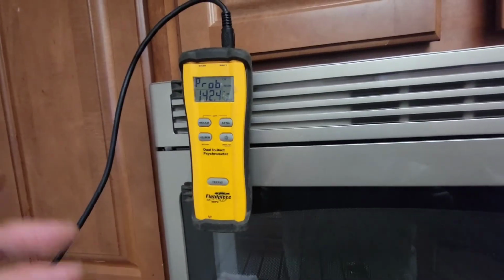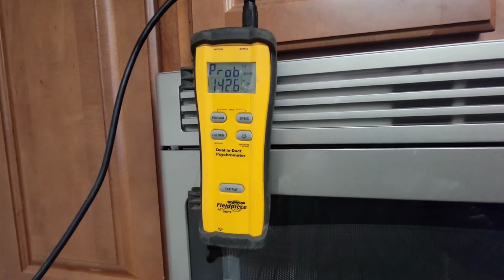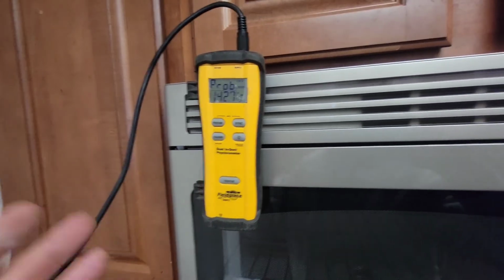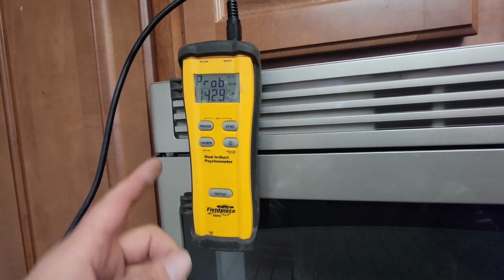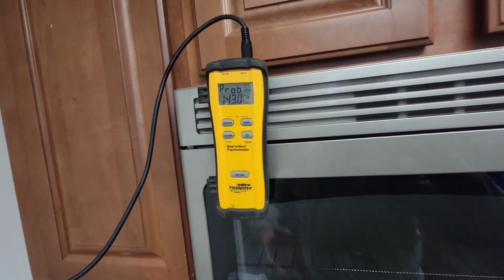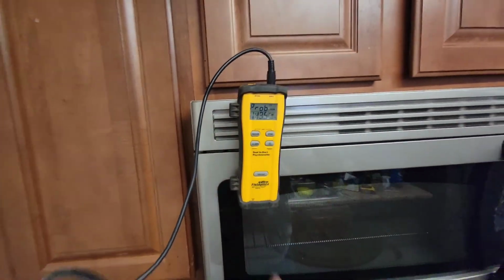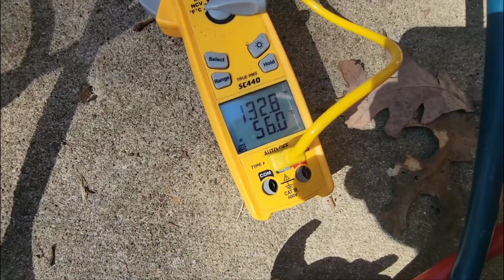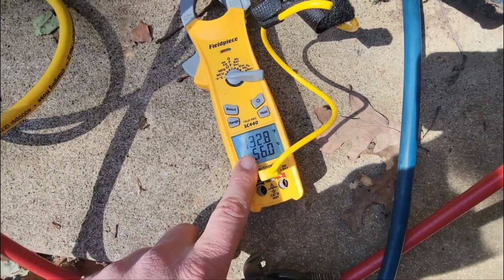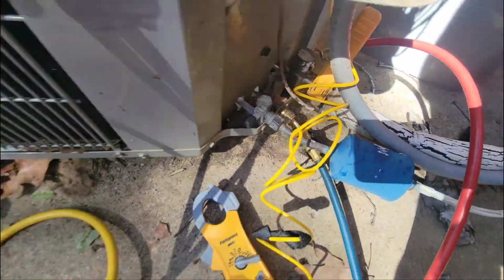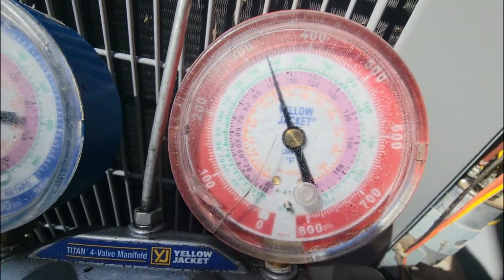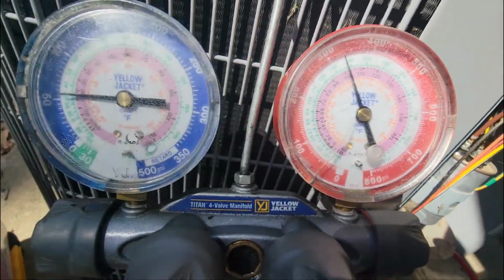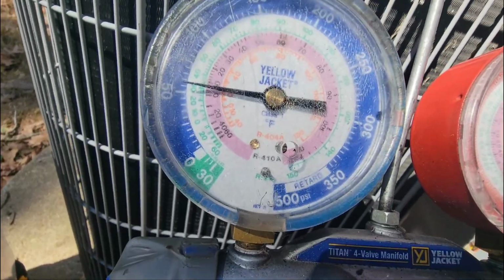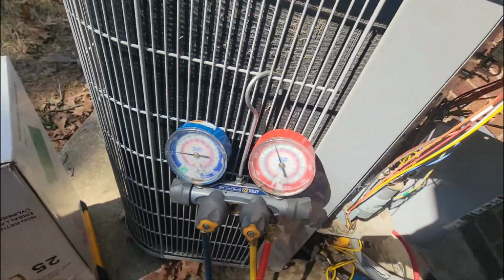So you want the true reading of just the heat pump. You want to make sure it's at least a 20 degree split. You need to disconnect the heat strips, and I've got a video on that. So I'll drop that link in the description, but it's definitely heating. Let's check out that indoor air handler. Before we do that, 132 degrees on the vapor line. High side is 325, 330. Low side is about 55, 60.